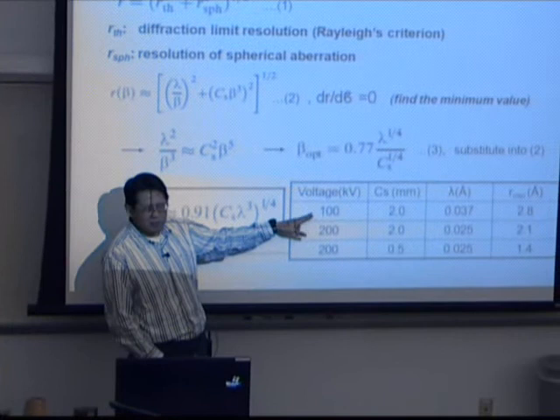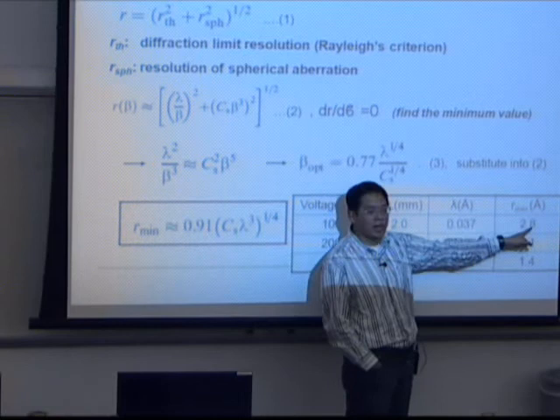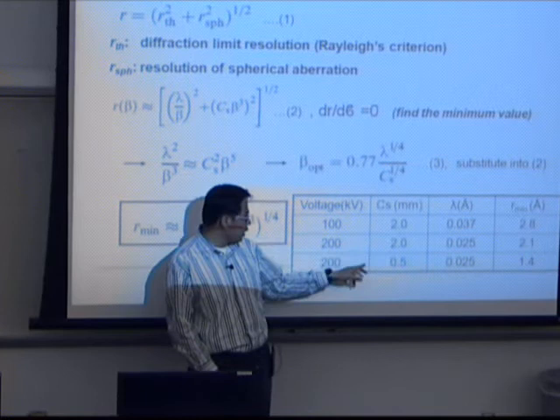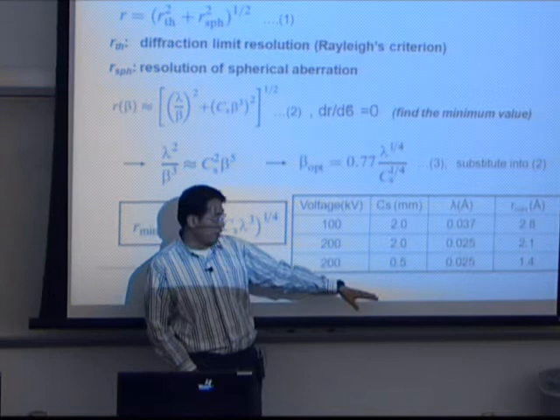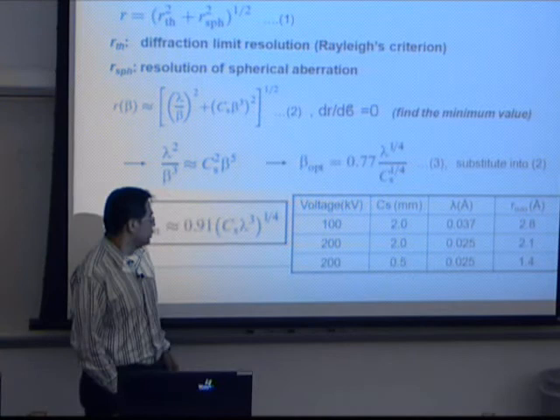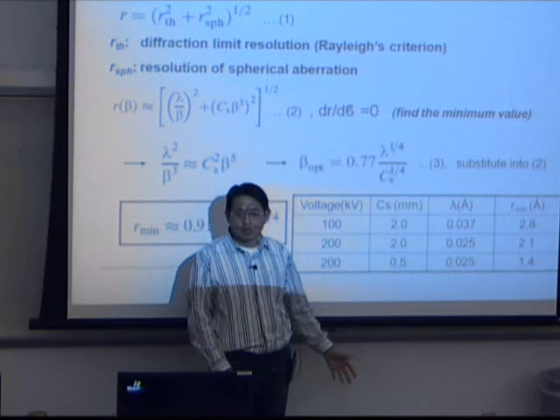For example, if you only increase the energy of the electron, you can only improve the resolution from 2.8 Angstrom to 2.1 Angstrom. But if you reduce the spherical aberration coefficient C_s from 2 to 0.5 — which is what we have in our NISP lab downstairs — we can improve to 1.4 Angstrom resolution. Nowadays, if you want sub-Angstrom resolution, it would probably cost one or two million dollars to set up a system that corrects the spherical aberrations.